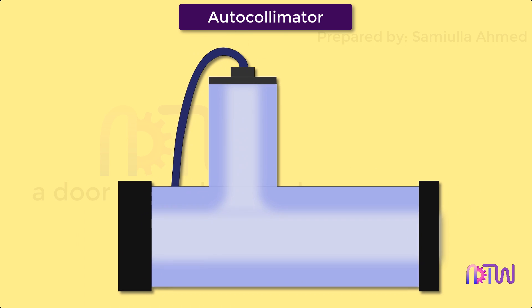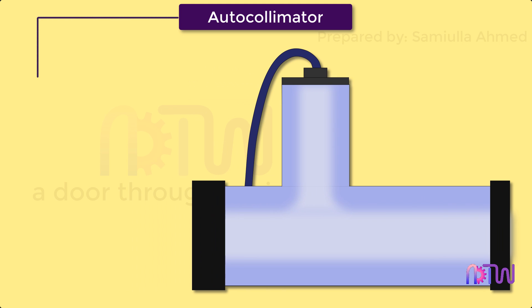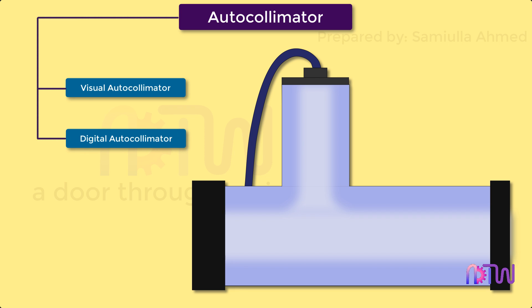An autocollimator is an optical instrument. It is a non-contact type instrument which is used for measuring angles. They are used to align components and measure deflection in optical or mechanical systems. There are basically two types of autocollimators: Visual Autocollimator and Digital Autocollimator. This video covers the Visual Autocollimator.